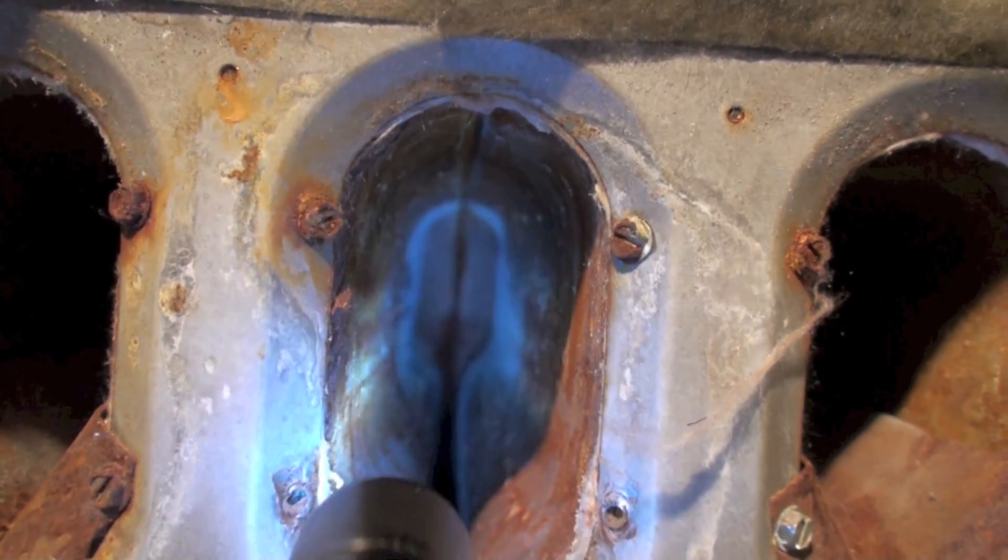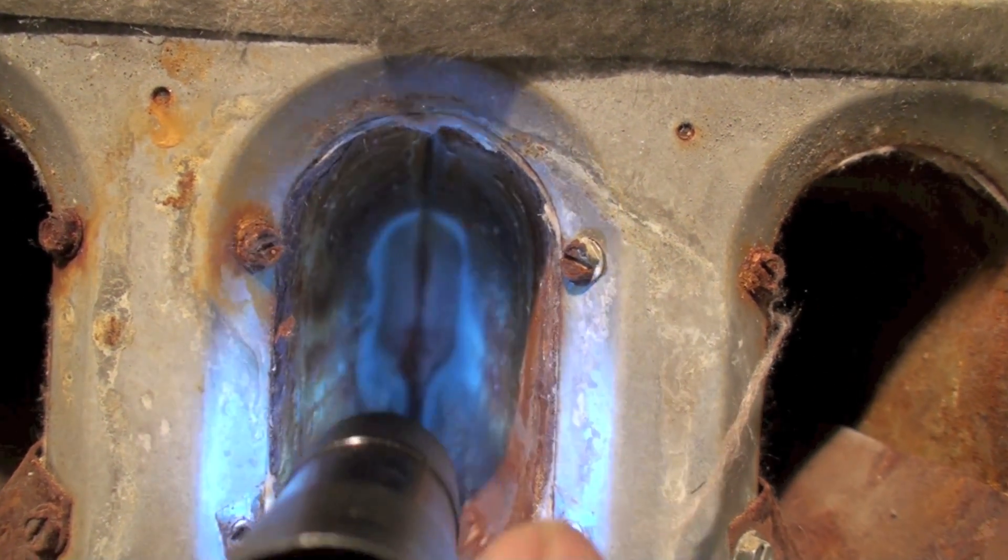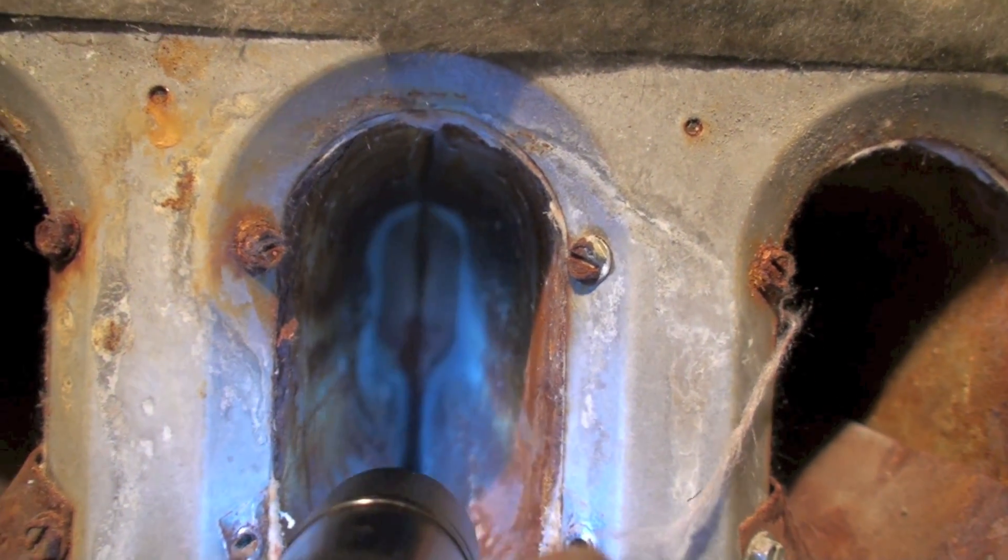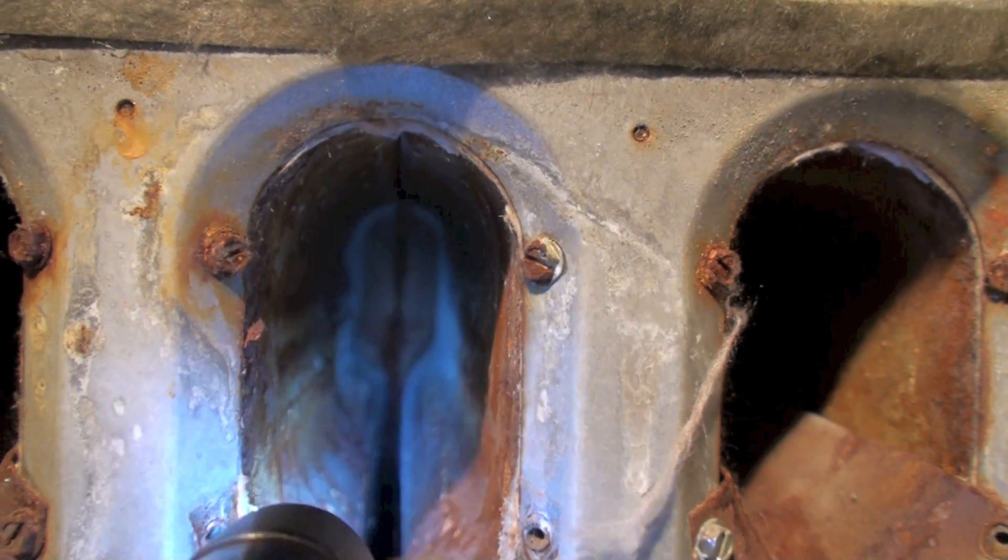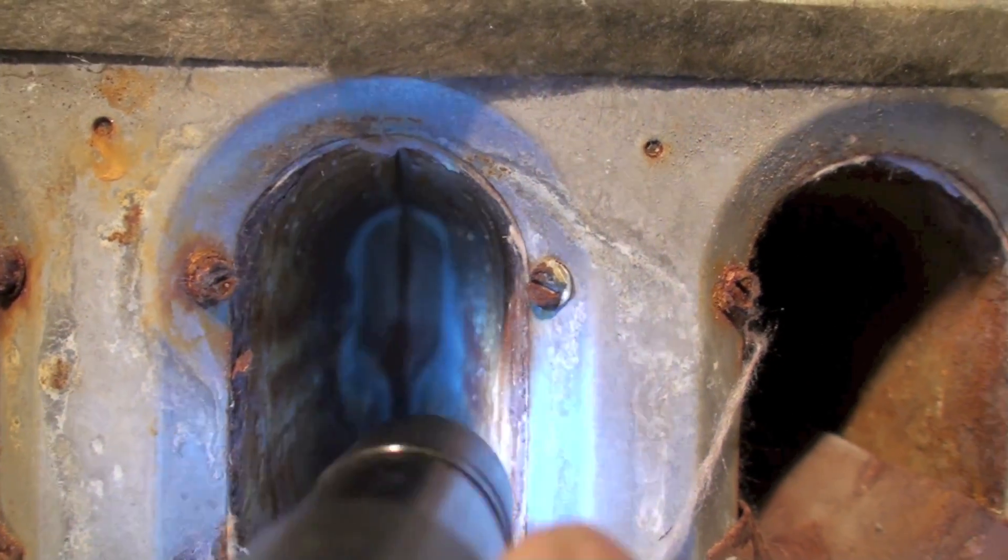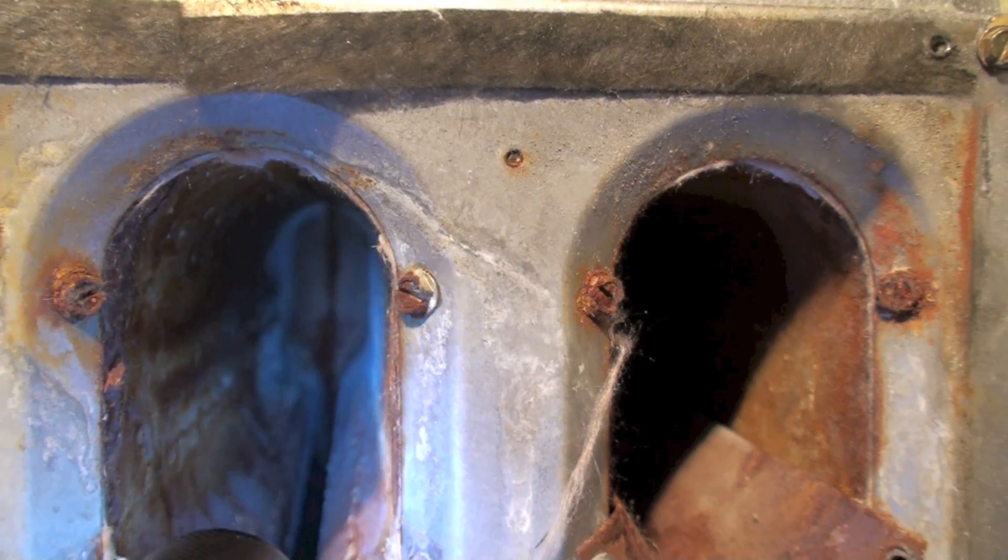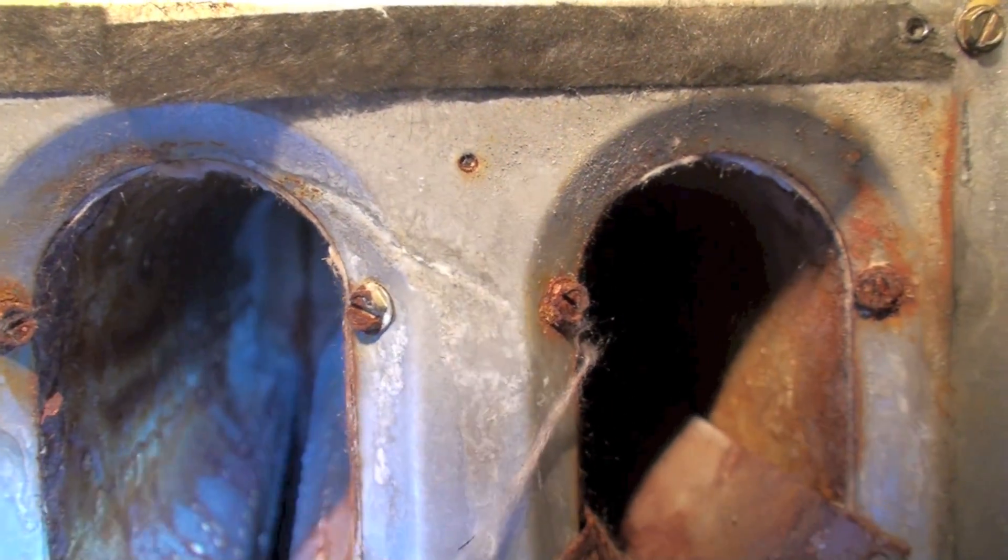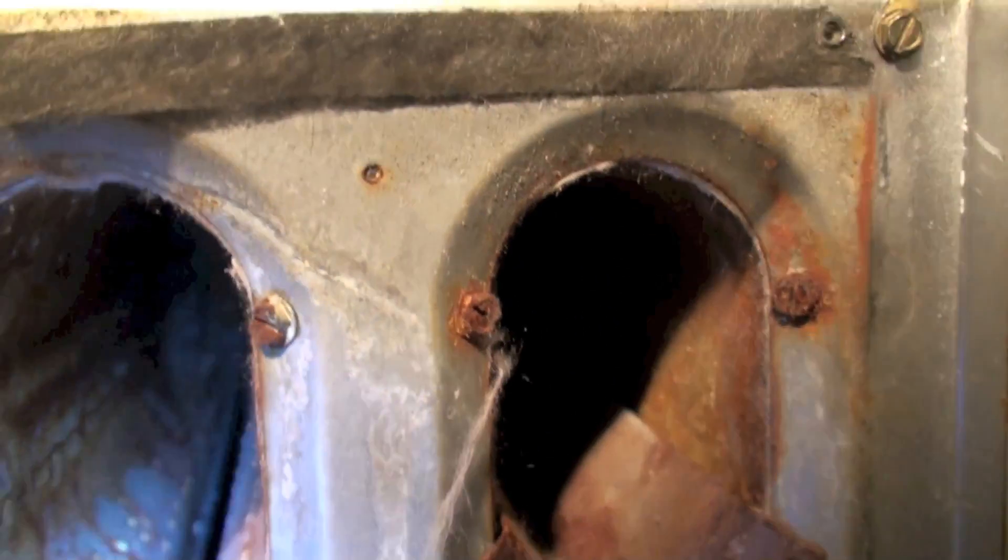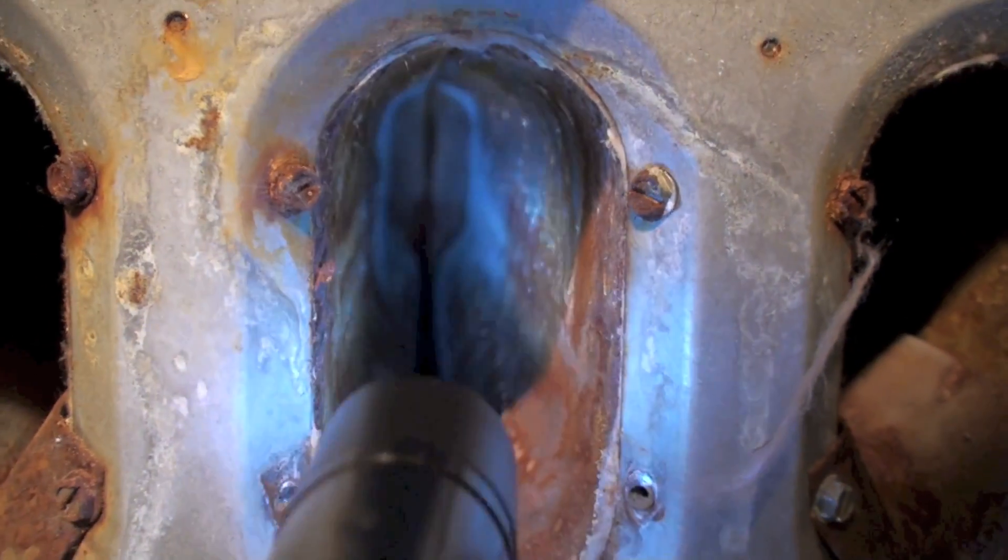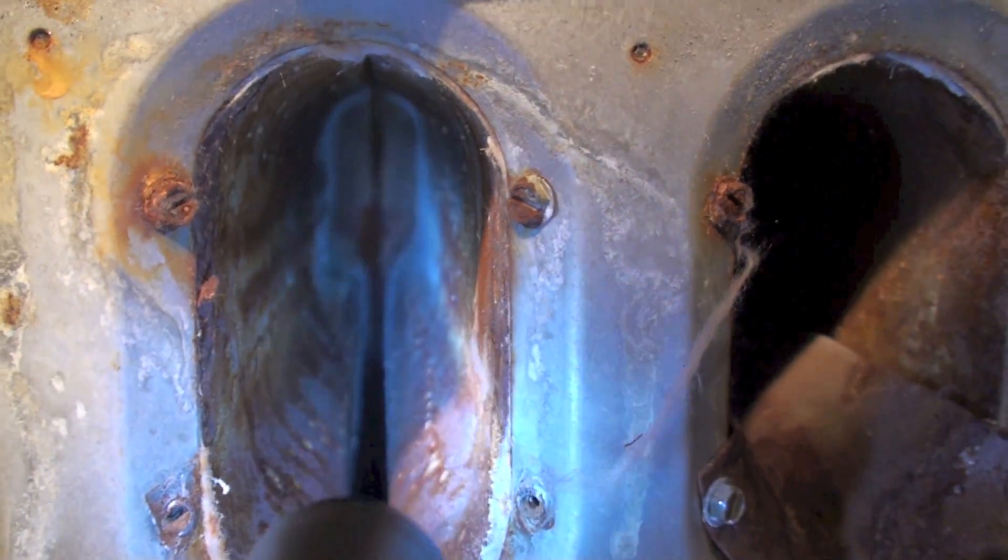Once that baffle's out of there, take a long skinny brush, something like that, and just thoroughly brush in there. That should probably take care of it. Make sure there's no cracks. You're always looking for cracks in heat exchangers or rust out spots or something like that.